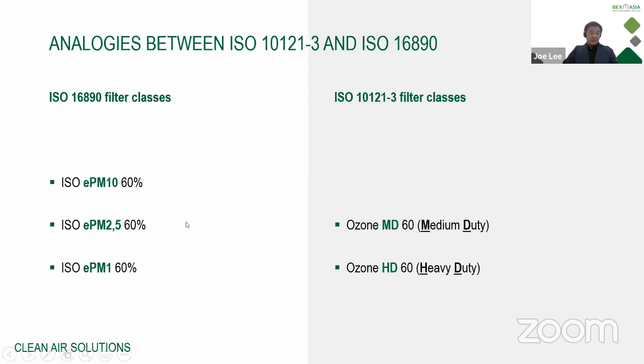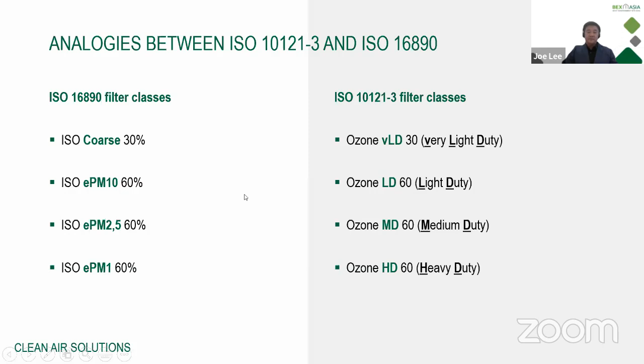And well, take note, even for this particular filter, maybe for ozone it can do HD 60, but for the other gases like maybe SO2, it might not be the same kind of classification. So ePM2.5 60% will give you ozone MD 60%, medium duty. The next level will be ePM10. You can see it is ozone LD 60%. Last but not least, coarse 30% is actually VLD, very light duty 30%.